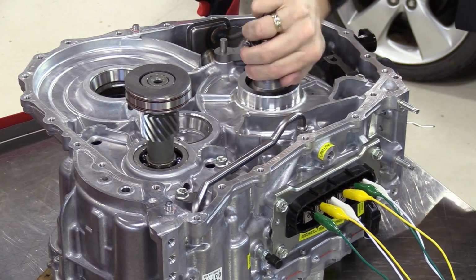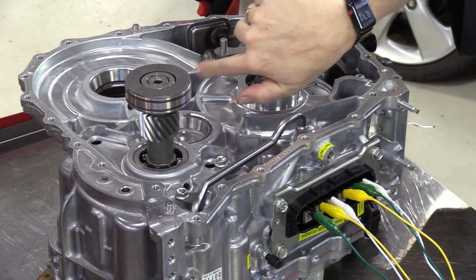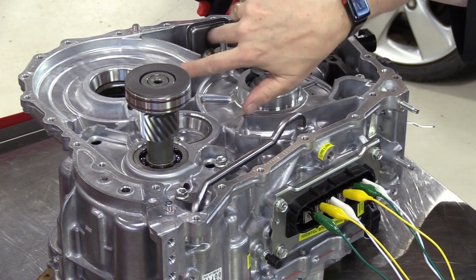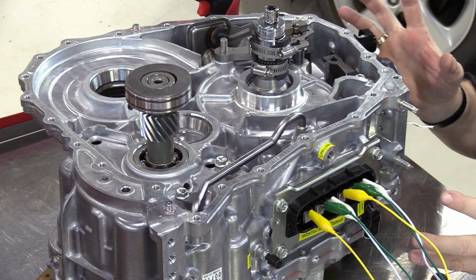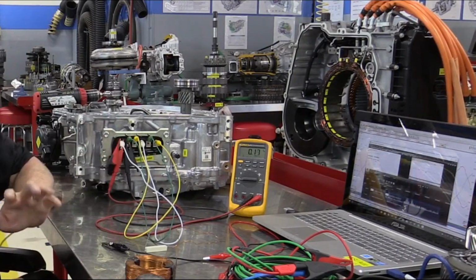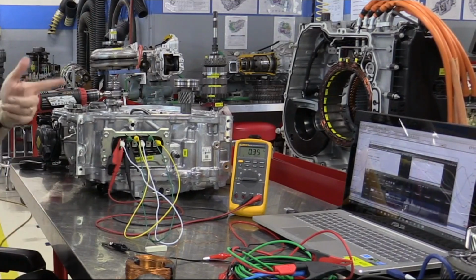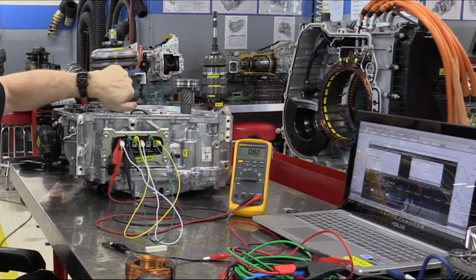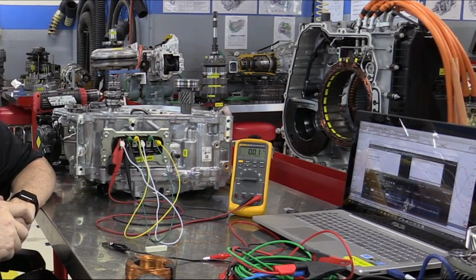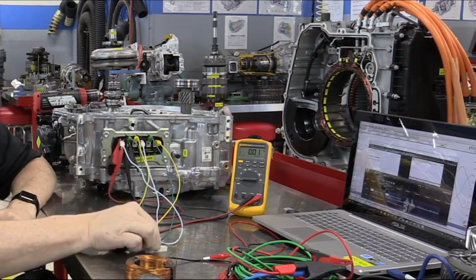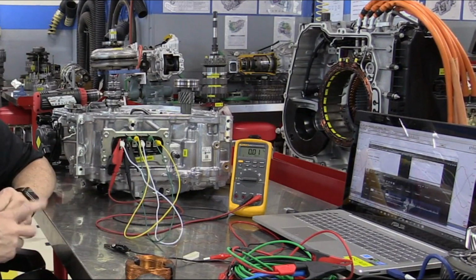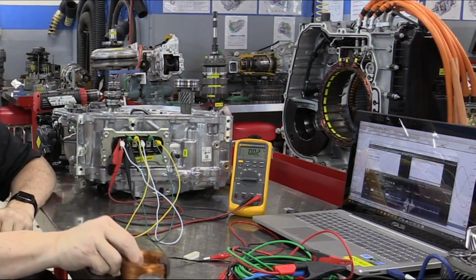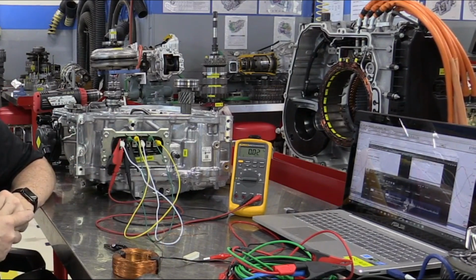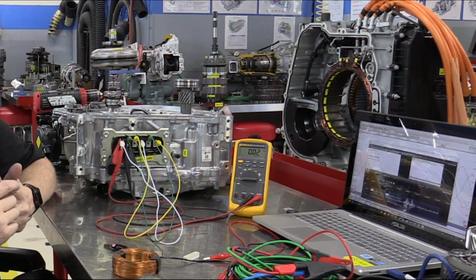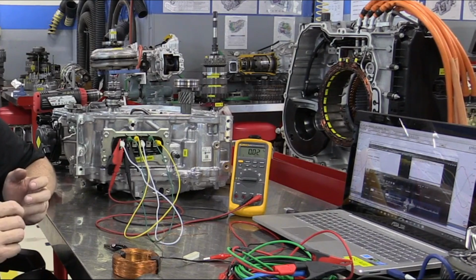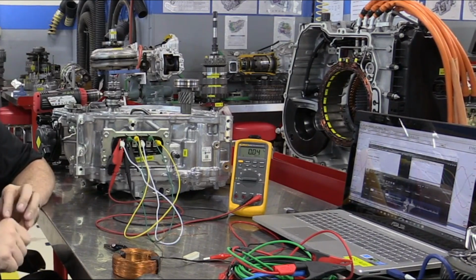The motor relies on a carefully balanced electromagnetic field generated by the stator windings to produce torque. With all windings shorted, this balance is lost. The magnetic field required for motor operation collapses, leading to an immediate loss of motor function. The imbalanced, erratic behavior of the remaining magnetic fields could cause irregularities and instability in motor operation if it does not fail outright. The short circuit will place a massive load on the power supply or battery system. If the system is not equipped with a fast-acting protective device, the power supply could suffer damage due to the overload. This can manifest as a tripped circuit breaker, blown fuses, or permanent damage to the power electronics such as the motor controller or inverter in an EV.